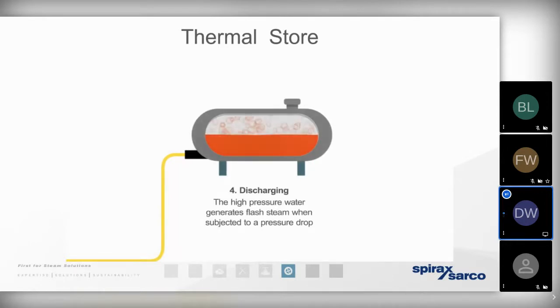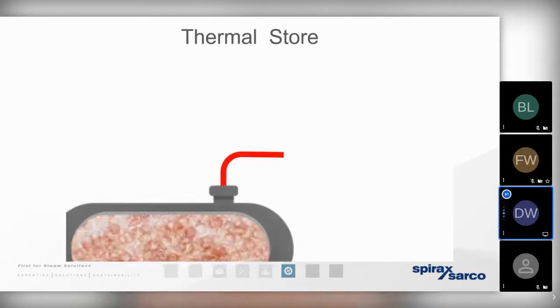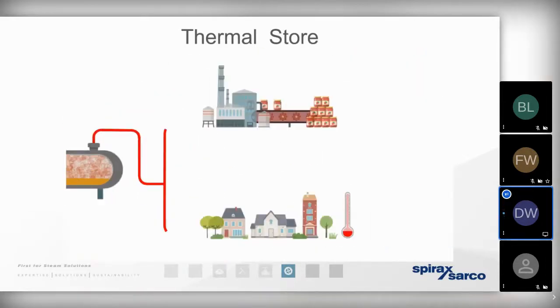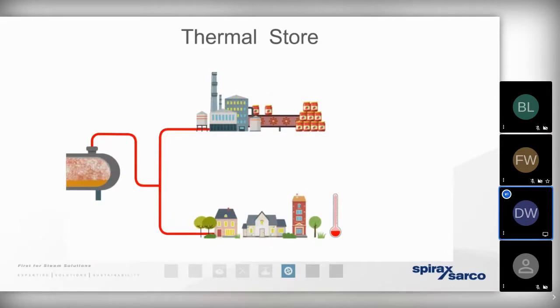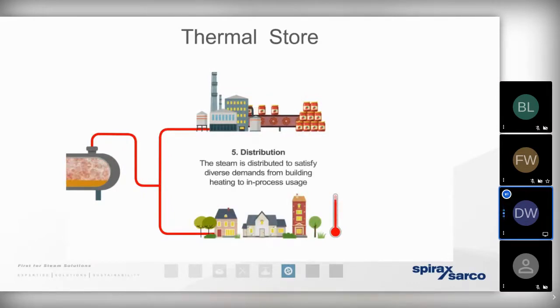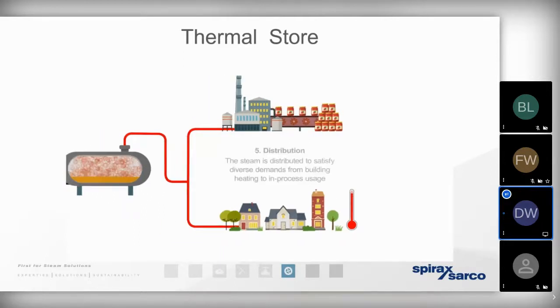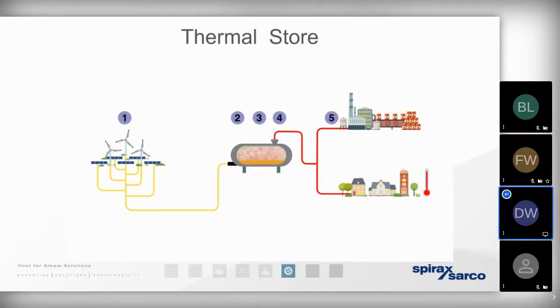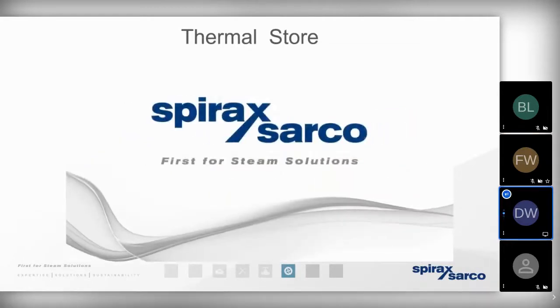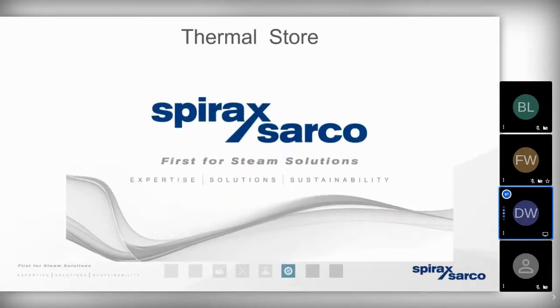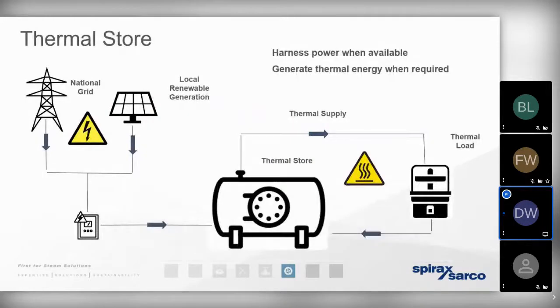If we've got a volume or a mass of high temperature, high pressure hot water that's held in storage until it's required, well, simply by reducing the pressure of that pressurized hot water, we're going to produce that flash steam that we've spoken about. And we know from previous presentations that there's just as much energy present in flash steam as there is in plant steam. And that can be taken away to satisfy a number of different processes.